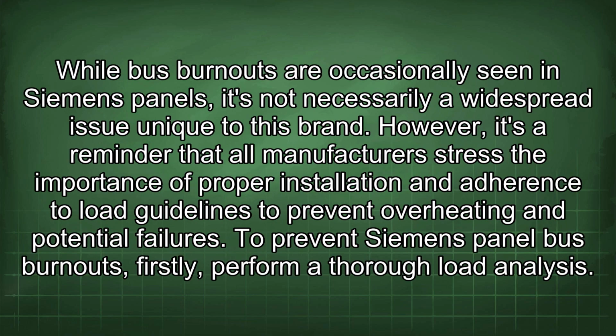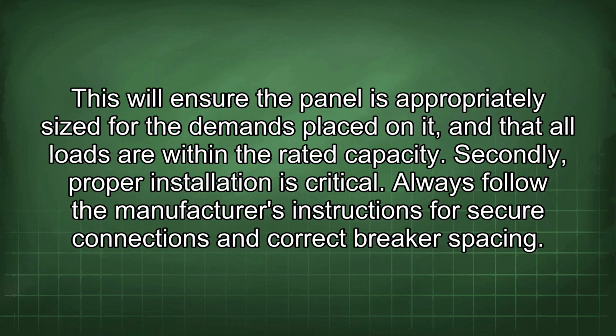While bus burnouts are occasionally seen in Siemens panels, it's not necessarily a widespread issue unique to this brand. However, it's a reminder that all manufacturers stress the importance of proper installation and adherence to load guidelines to prevent overheating and potential failures. To prevent Siemens panel bus burnouts, firstly, perform a thorough load analysis. This will ensure the panel is appropriately sized for the demands placed on it, and that all loads are within the rated capacity. Secondly, proper installation is critical.